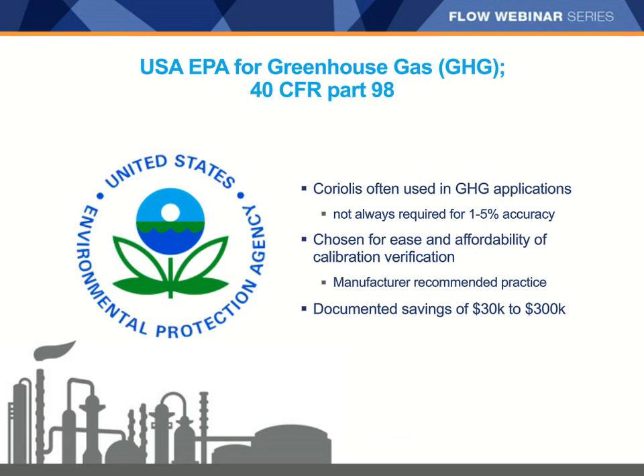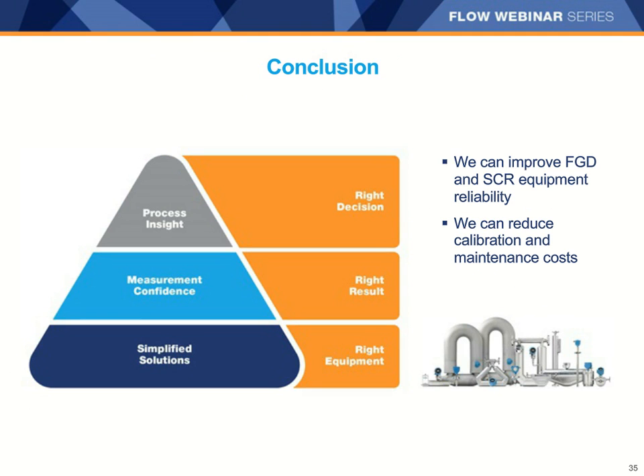Micromotion smart meter verification is recognized by the U.S. EPA as a way to meet 40 CFR Part 98 of the Clean Air Act while extending calibrations. In addition, the EPA is currently evaluating smart meter verification technology to extend calibration intervals in other parts of the 40 CFR statutes, like 40 CFR Part 75. Some users have saved up to $300,000 per year on reduced or eliminated calibrations. There are a number of third-party organizations that currently accept or are evaluating our smart meter verification for acceptance.